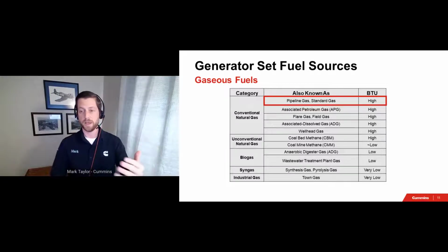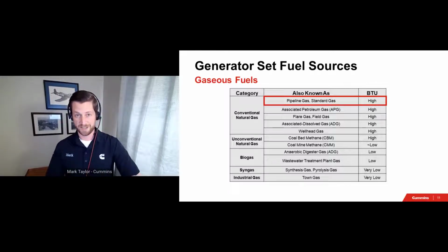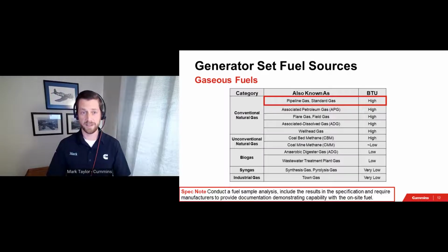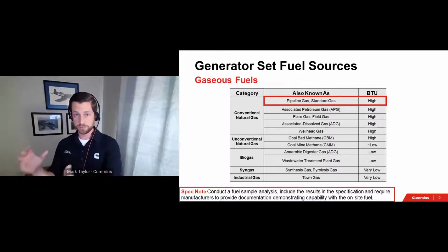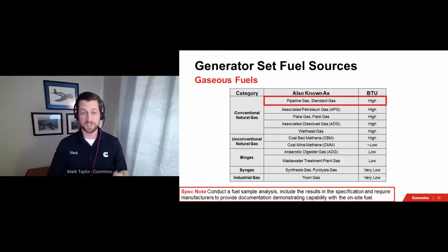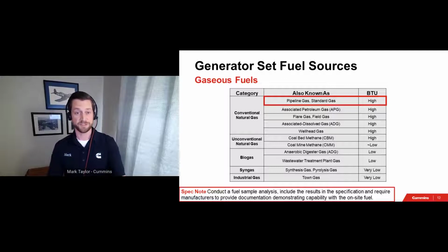Compared to its peers, though, pipeline natural gas is generally high energy and freer of contaminants. That being said, natural gas cannot be assumed to be of a perfect standard composition. Gas constituents will vary by geographical area. Its composition can vary if it depends on, for example, a single wellhead that might be aging, as opposed to a network that draws from multiple sources. Though pipeline natural gas is generally quite reliable in the United States, it never hurts to conduct a fuel analysis to be sure of the energy content if there is ever any doubt. Cummins will be glad to assist in interpreting the results of a fuel analysis with you.